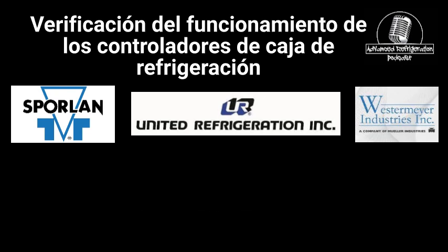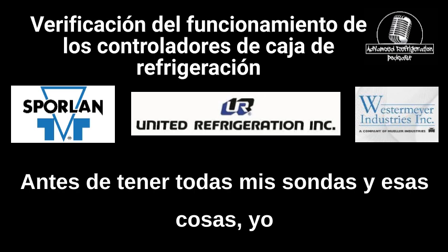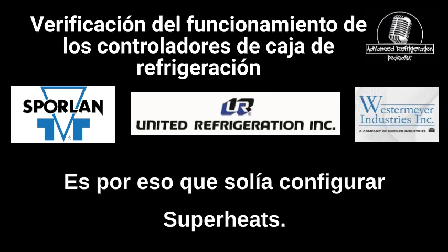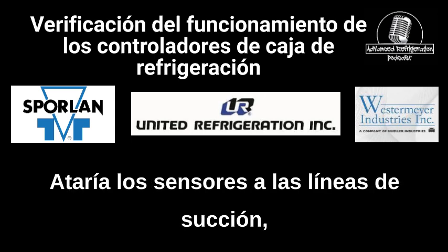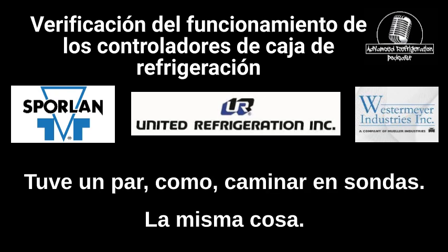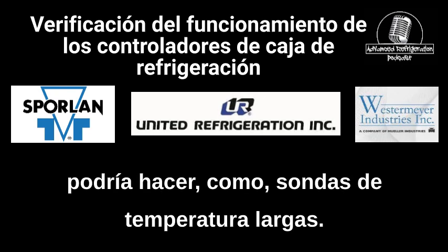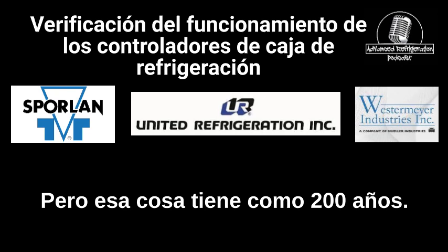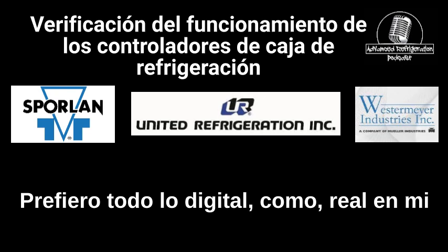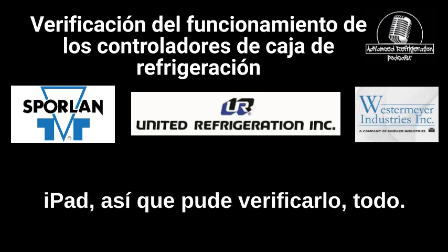Before I had all my probes and stuff, I had my Cooper Red Box and I had 4 CPC sensors with 20-foot leads on them. That's how I used to set superheats. I would strap the sensors to the suction lines and use the Cooper Red Box. I had a couple of walk-in probes too, so I could do long temp probes. It worked great. I mean, that thing's like 200 years old. I prefer everything digital, like on my iPad, so I could just verify everything.